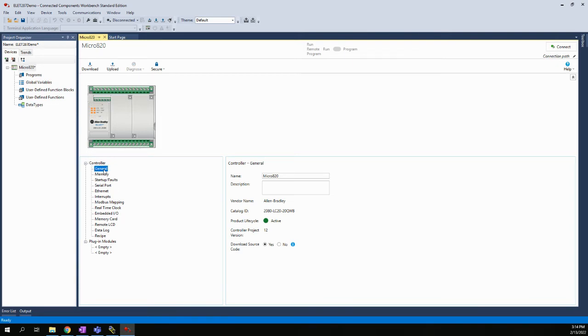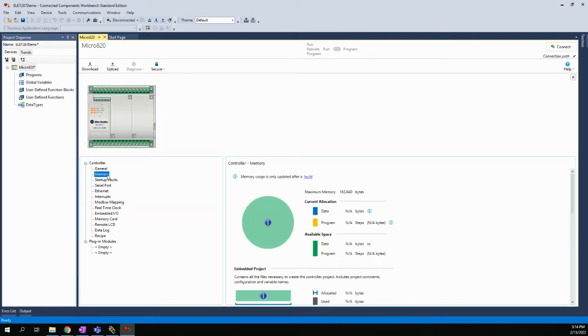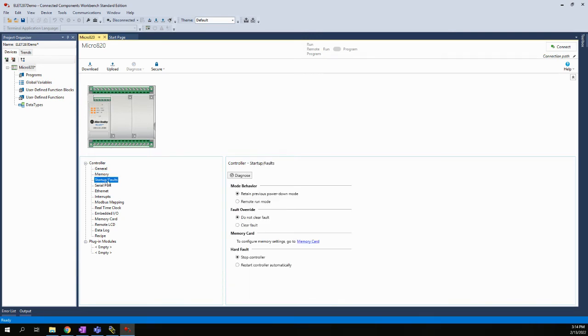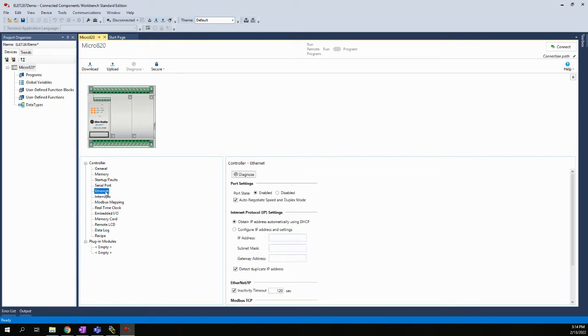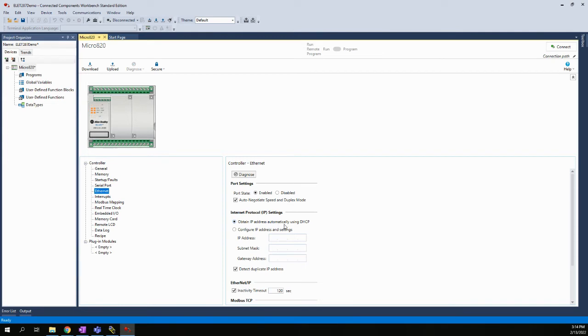And then we have whatever kind of general configuration properties underneath this tree structure here. So that's our general, we have memory. So many things we may not be able to change. It might just be more information, but this just tells you about the amount of memory you have in a controller, maybe what's been used. Startup, serial port. And what we really need to worry about, at least at this point, is the Ethernet port. Because by default, when we create this project, there is no Ethernet settings in here. As a matter of fact, it's kind of like we talked about in the setting your IP address on your laptop. It's defaulted to obtain IP address dynamically or automatically using the DHCP, or the Dynamic Host Configuration Protocol.